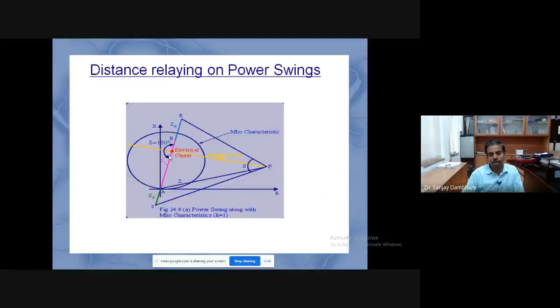And this is a transient phenomenon. It cannot stay there for a long time because the system is oscillating, right? The system is oscillating, and this is called the electrical center. So at the electrical center, certainly your relay will take it as a fault. So obviously the system may lose transient stability, but the relay will have to operate.